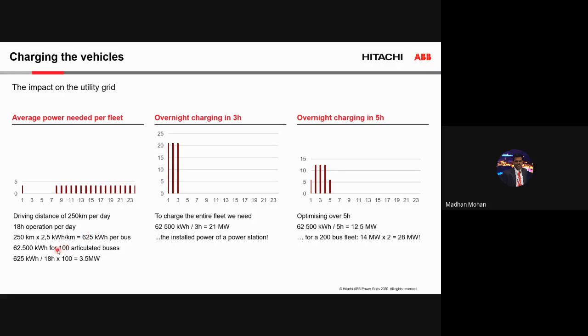Now say you operate 100 buses for 18 hours each - the total power demand for the fleet works out to 3.5 megawatts. If you put all 100 buses into a depot charger overnight for 3 hours, the peak demand to the grid becomes 21 megawatts. If instead you charge for 5 hours rather than 3, the demand reduces to 12.5 megawatts. This shows the huge peak power demand to the grid when using overnight charging of 3 or 5 hours.